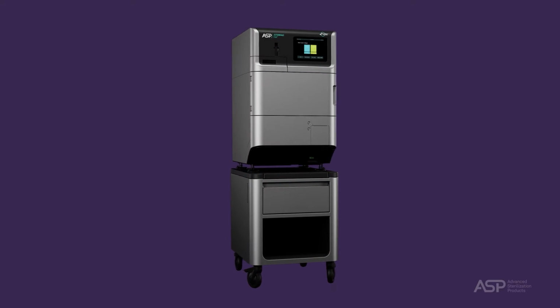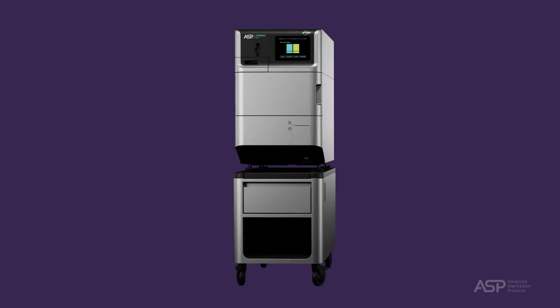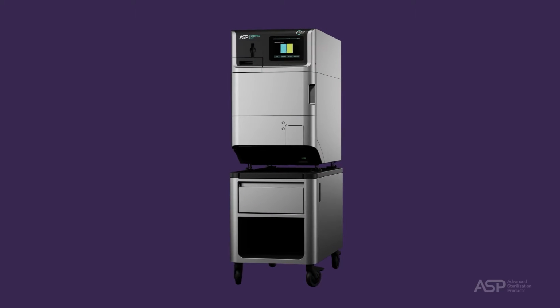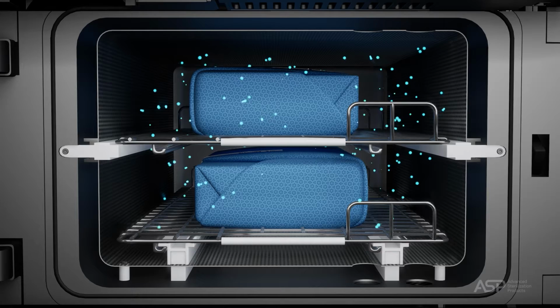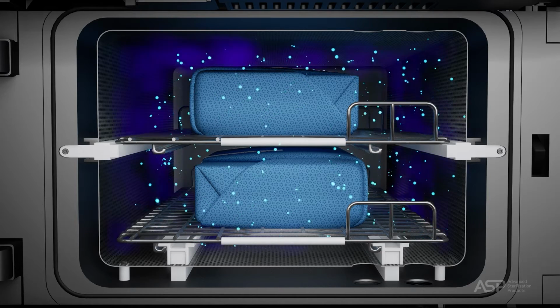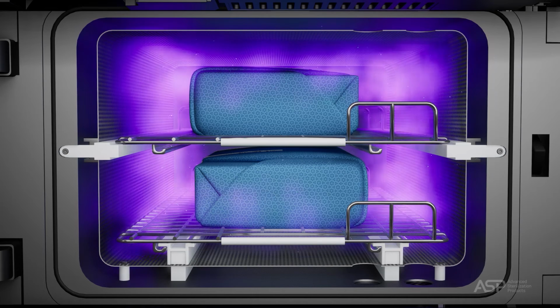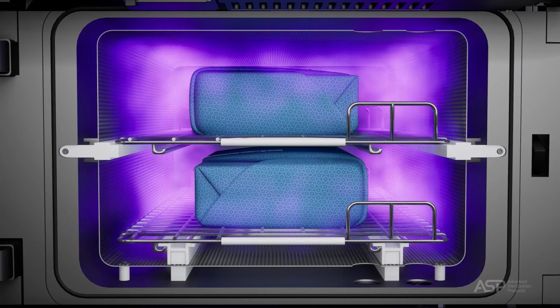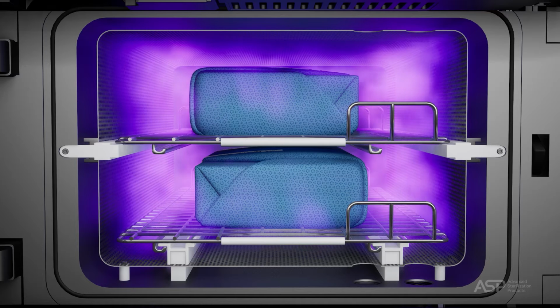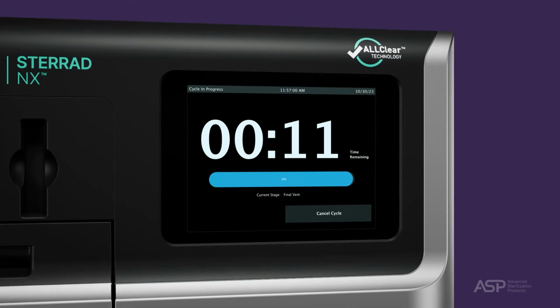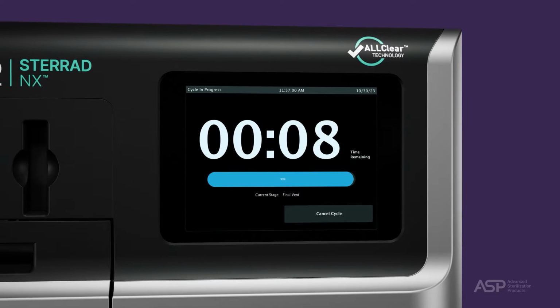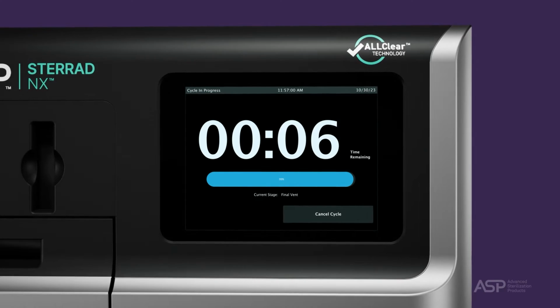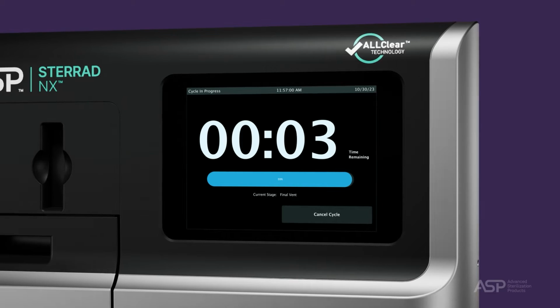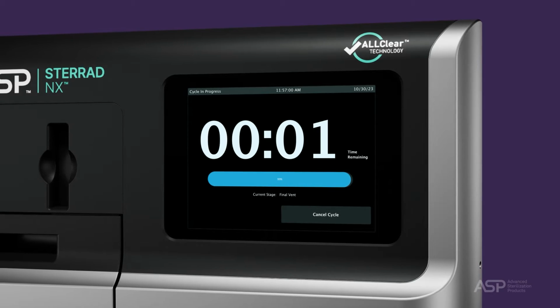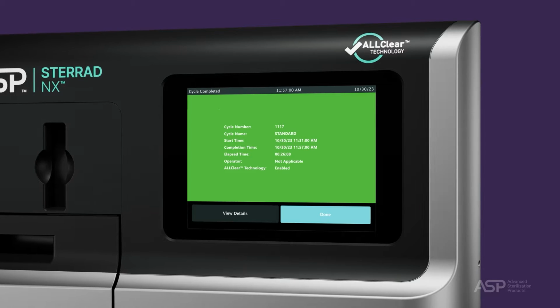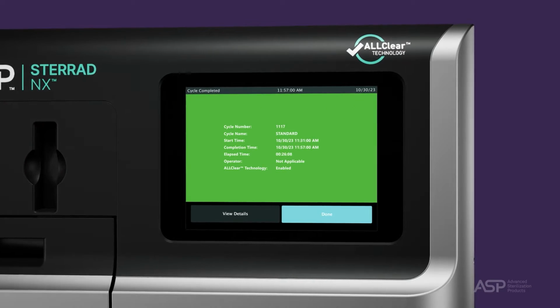The STERRAD NX sterilization system with ALLClear technology is a general-purpose, low-temperature sterilizer that sterilizes medical devices by diffusing hydrogen peroxide vapor into the chamber, and then electromagnetically exciting the hydrogen peroxide molecules into a low-temperature plasma state. The combined use of hydrogen peroxide vapor and plasma safely and rapidly sterilizes medical instruments and materials while minimizing exposure to toxic residue. All stages of the sterilization cycle operate within a dry environment at a low temperature, and thus the cycle is not damaging to compatible instruments that are sensitive to heat and moisture.